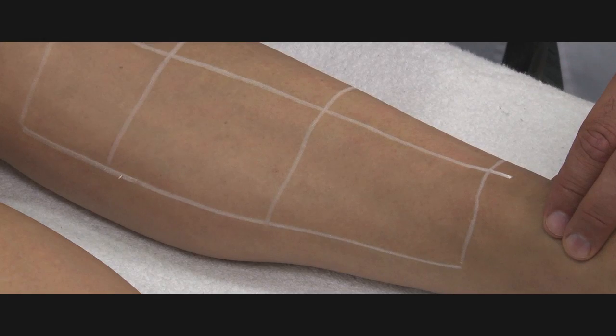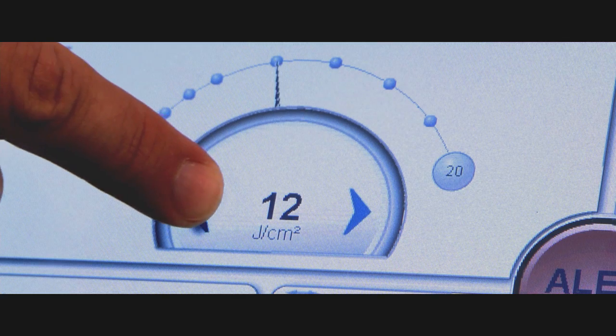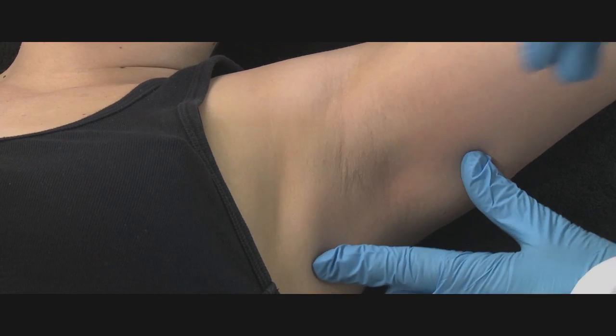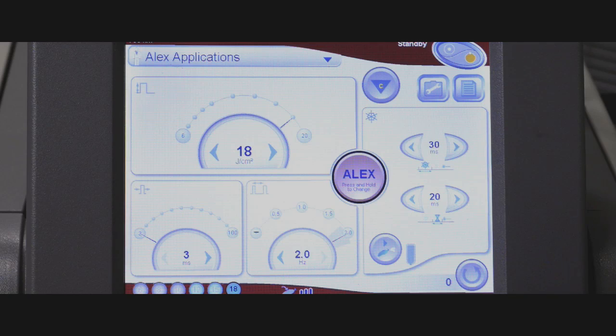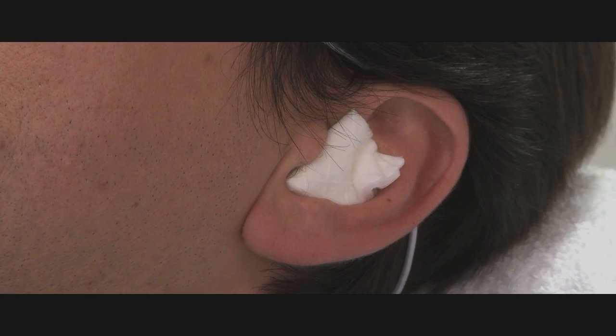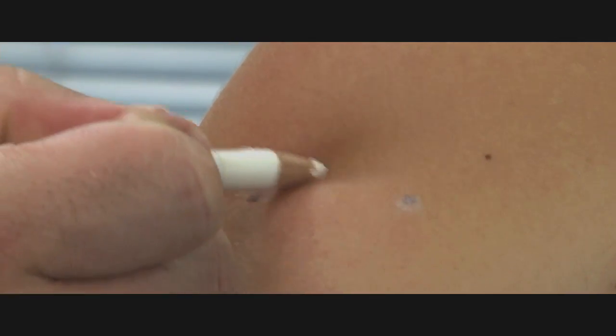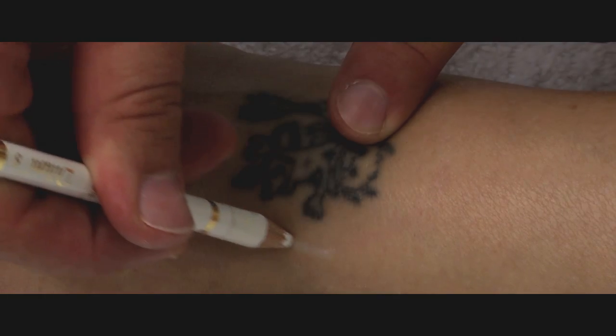For larger zones, you may wish to mark the zones in order to more easily remember which area has been treated. Remember to lower the energy by two joules over bony areas. Also remember that areas with more pigmentation, such as the genital or axillary region, will require a change in parameters based on the level of pigmentation. Be sure when pulsing near orifices such as the nose or ear that they are covered with multiple layers of moist white gauze. Also be certain to avoid lentigos, covering them with white pencil and/or white paper as needed. Remember to keep a 1 centimeter distance around tattoos. The long pulsed laser can be used to treat benign pigmented lesions, but never tattoos.